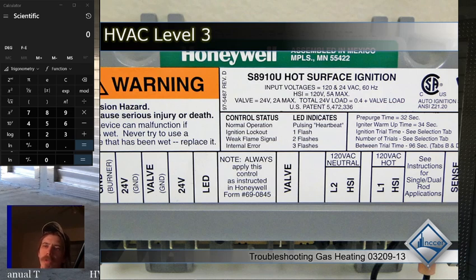But if you think it's poorly calibrated or a bunk thermistor straight from the factory, you can verify that by calculating your voltage drop and checking the voltage across it, or by sticking it in some ice water and comparing the resistance, which is generally what they recommend. They usually don't try to get you to do it based on voltage drop. But there have been a couple times I've been troubleshooting a board and had to see what the voltage was there to verify operation. So, sorry for my lack of memory there. I'll go back tonight and try to remember how to calculate voltage drop so I don't mess that one up again. All right.